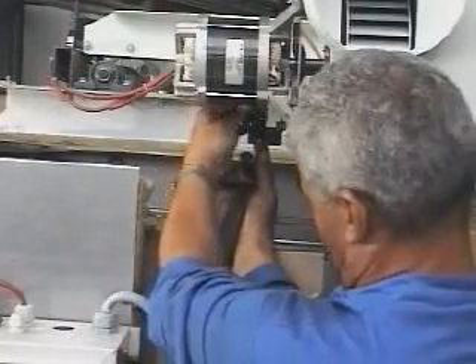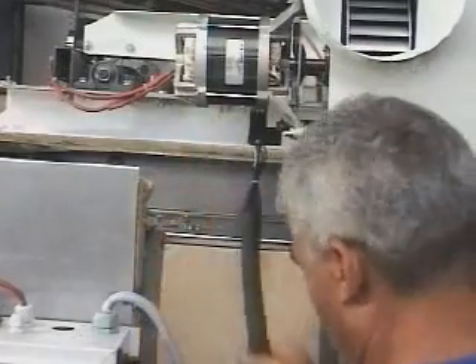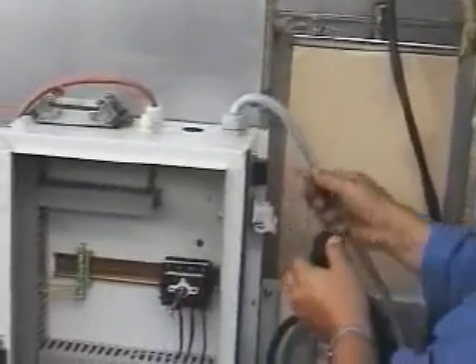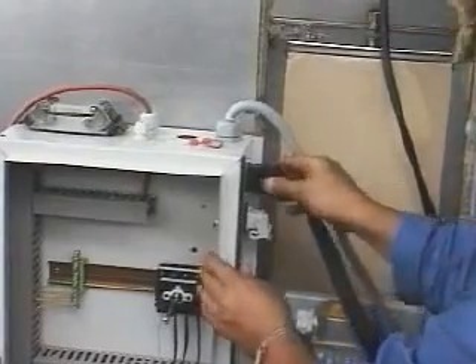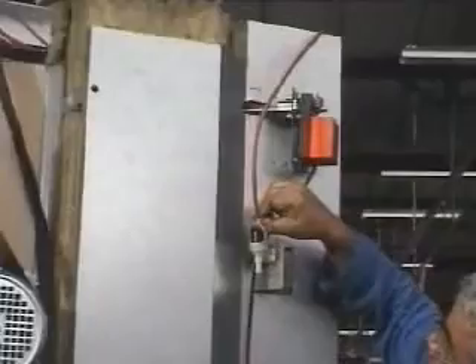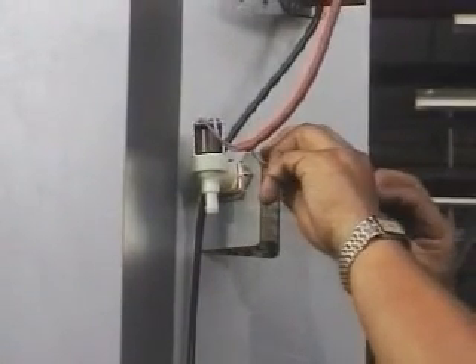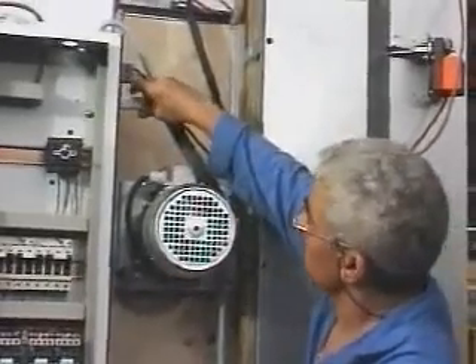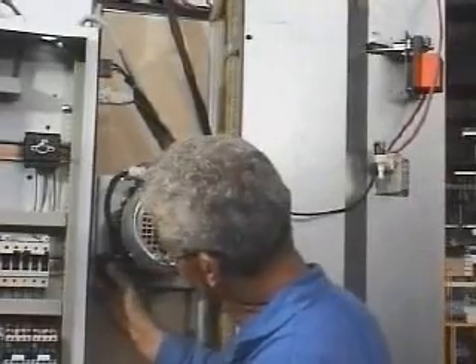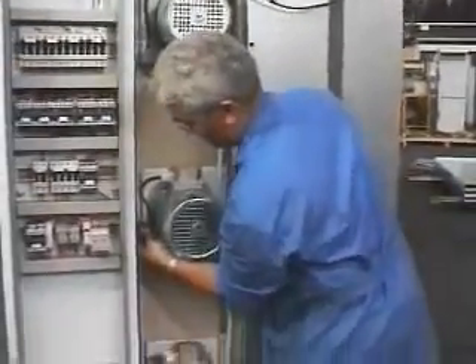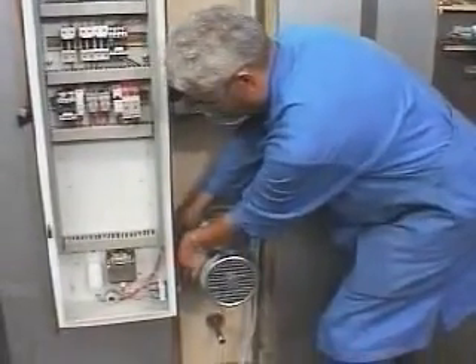Using the plugs and sockets provided, connect up the extractor motor, the solenoid valve, the steam extractor motorized reduction gear clearance and the fan motors. Interconnect the front panel, the electric cabinet, the top components and, depending on the version, the heating elements.